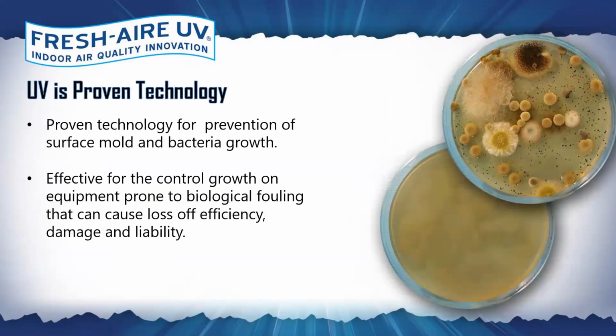Now, this is a test I've done hundreds of times, one I always enjoy doing. Oftentimes I'm visiting facilities, could be a school, could be a healthcare facility, and I meet with the facility director. And we have a frank conversation about the nature of their air handling unit, what they may have as far as growing inside their air handlers. And oftentimes they're very proud of the HVAC equipment, and they take me to see the facility, and they take me to see the air handling unit. They turn it off. We walk inside, and yes, the air handler itself, the coil may look clean, but that's either the leading or trailing edge of the evaporator coil. It's the tip of the iceberg, so to speak.